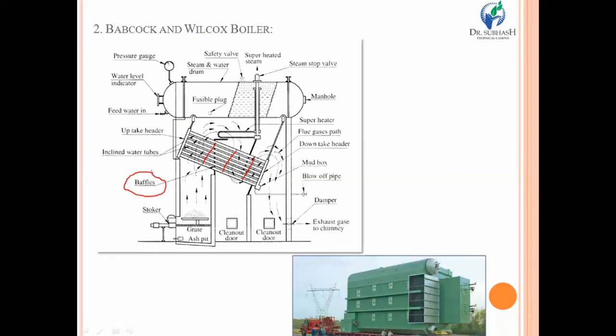The basic function of baffles is to provide equal distance between all the inclined tubes, and another function to be fulfilled by the baffles is to increase the length of the path of the flue gases that are being passed through these evaporator tubes.